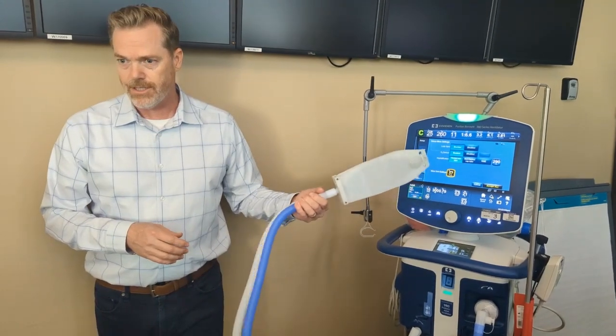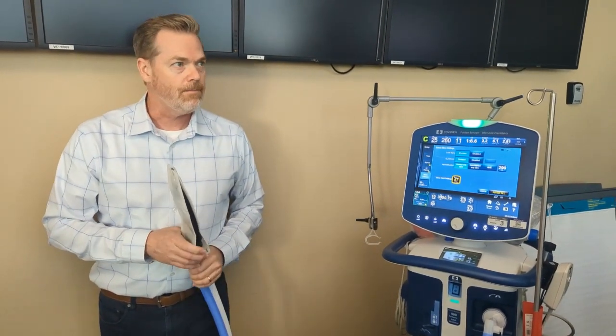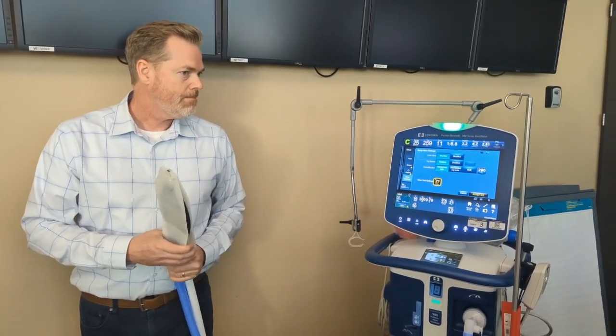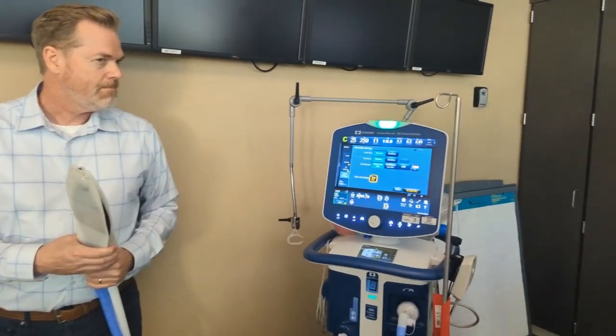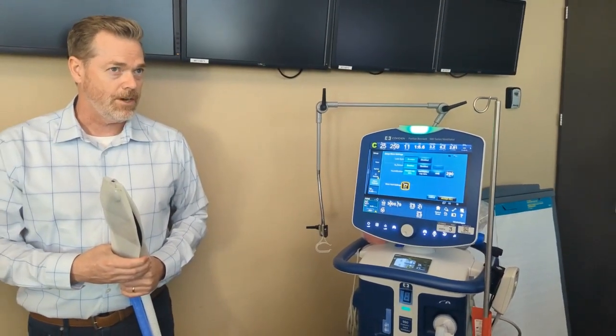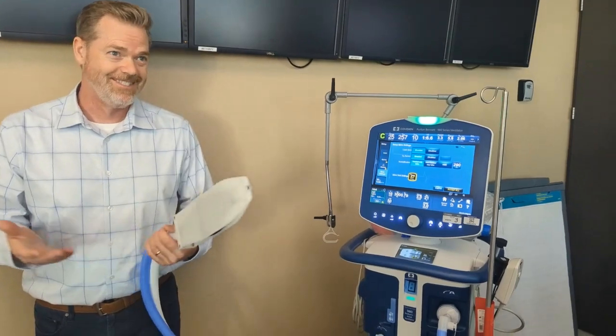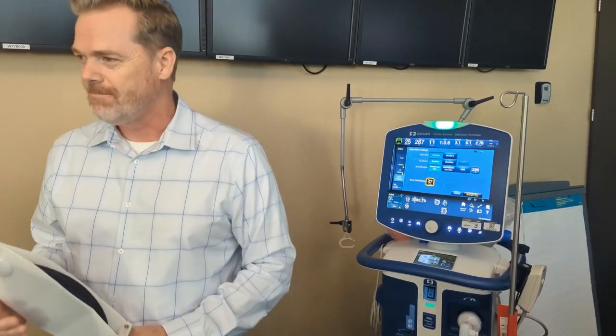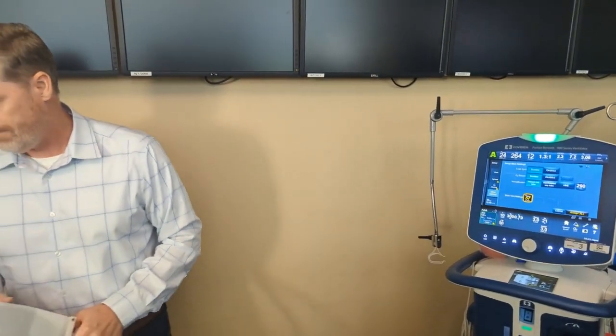High calibration is a little different. I always like to check that. That's using O2, NO2, and NO. The hospital supplies the O2. We should have little green cylinders of NO2 and NO, and that's where we do high calibration. Have you ever done a high calibration? Yeah. Nothing else? You guys good? Good.